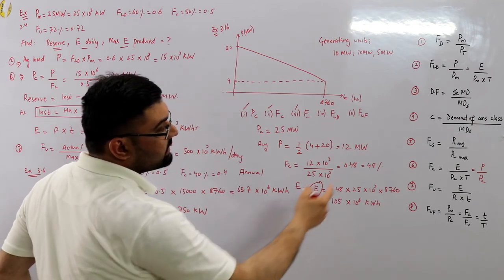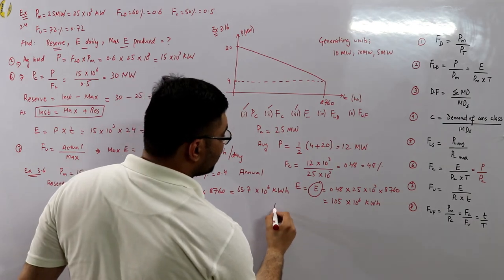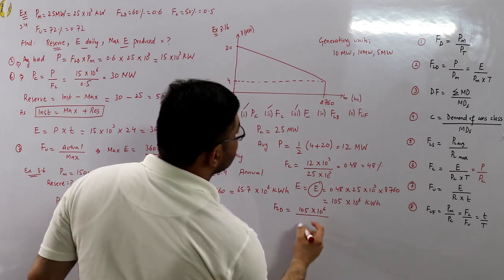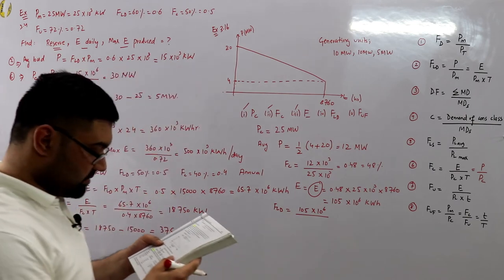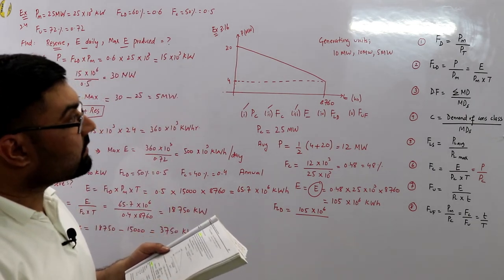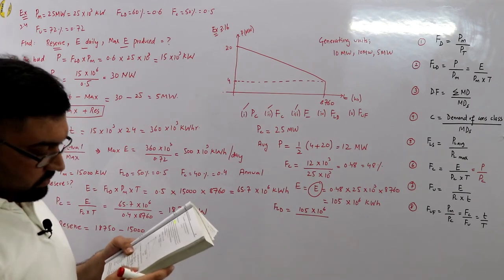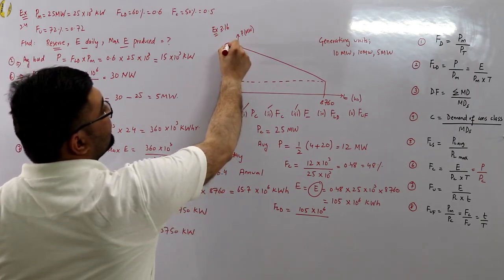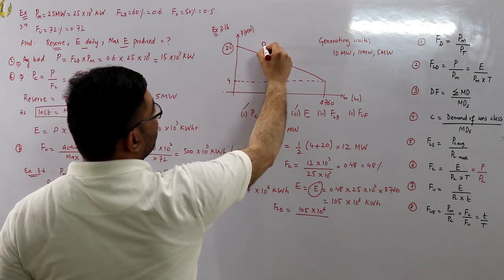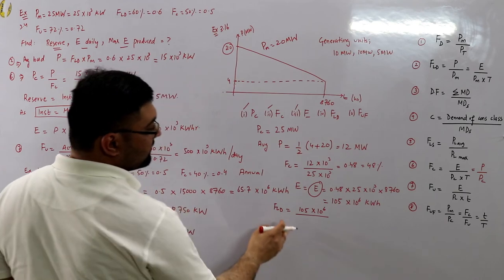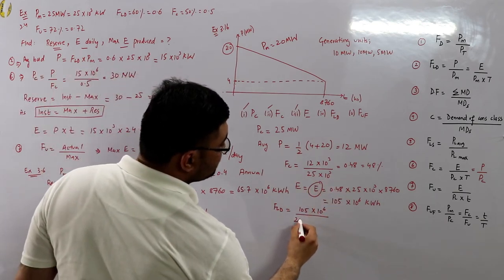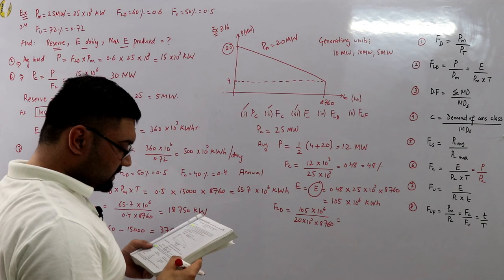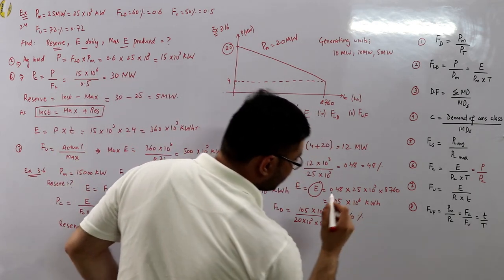The load factor FLD = E ÷ (PM × T) = 105×10⁶ ÷ (20×10³ × 8,760), or equivalently P ÷ PM = 12 ÷ 20. This comes out to be 60%.